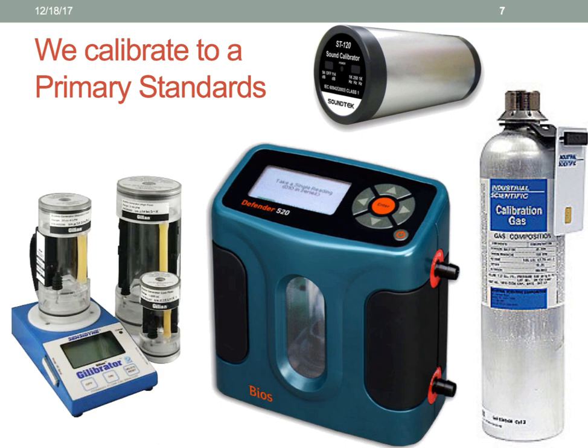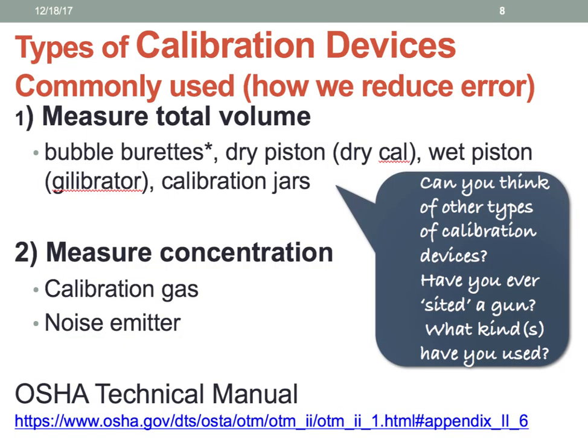So we calibrate to a primary standard. Here are some examples of primary standards: we have a piston calibrator or a dry cal, we have a gilibrator that is also called a bubble calibrator, then we have electrical devices such as our sound level meters, and then we have calibration gases. We calibrate to a primary standard to set and verify the rate at which the pump will pull air. You can check the OSHA technical manual link, which describes proper calibration techniques that we will use in this class.